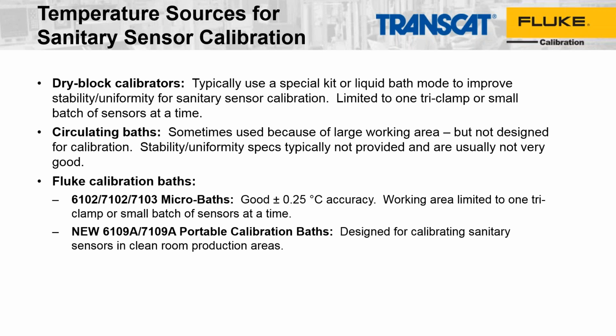And so then Fluke has a line of calibration baths that help cover the best of both worlds, where they are smaller and portable. We have two general categories. One is a product line that's been around for quite a while, the 6102, 7102, 7103 micro baths. We see these used all over the place. They're very popular.